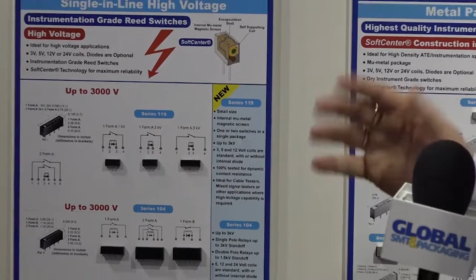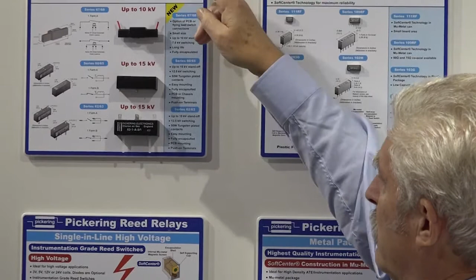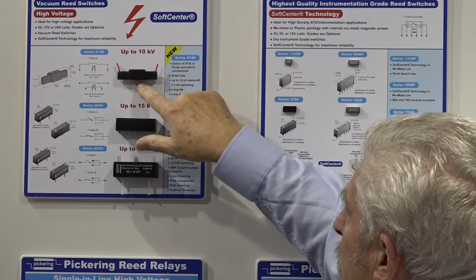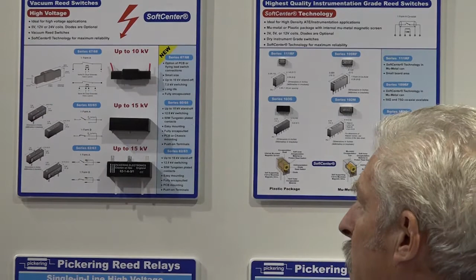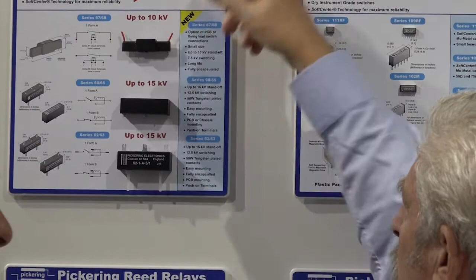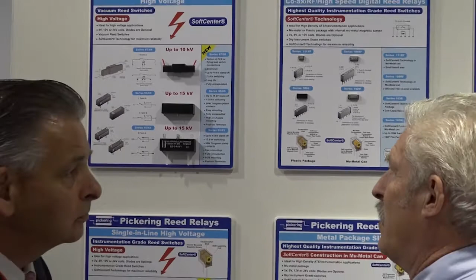If you move up in voltage, we've got the Series 67 and 68. There are two versions: the Series 67 is a PC board mounted relay, and the Series 68 has PC board pins for the coil and long flying leads for the EHT to keep them away from the PC board. These leads would normally be a couple hundred millimeters long to take them off to wherever the high voltage needs to go, to keep the high voltage away from the lower voltage PCB.